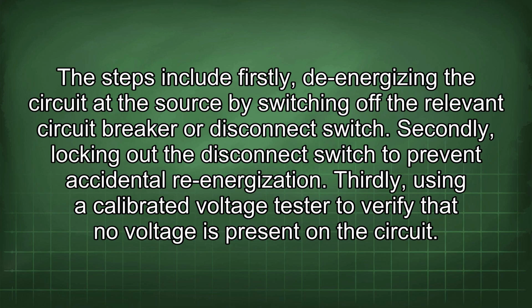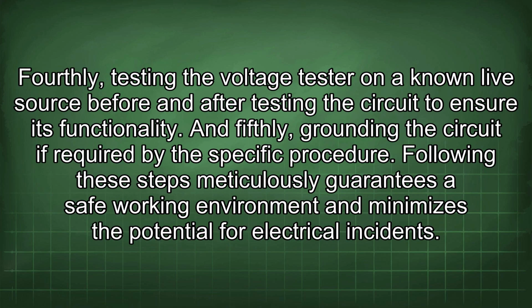Thirdly, using a calibrated voltage tester to verify that no voltage is present on the circuit. Fourthly, testing the voltage tester on a known live source before and after testing the circuit to ensure its functionality. And fifthly, grounding the circuit if required by the specific procedure. Following these steps meticulously guarantees a safe working environment and minimizes the potential for electrical incidents.